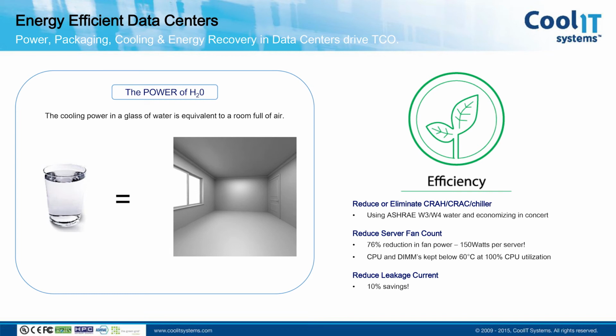That's right, and we'll often work up past 100 degrees Fahrenheit. 30 degrees seems to be what people ask us about, but we've worked as high as 40, 45 before. So it really is warm water cooling. And so for most, just being able to expel this into the ambient air outside is enough of a heat loss in order to be able to provide water below that temperature back into the system. Exactly. The primary cooling device, the facilities device that they need to cool that water, is a lot easier and more cost effective to operate when you need it to produce warm water.